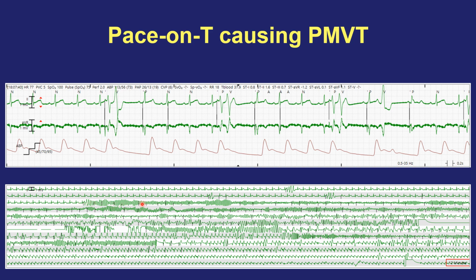Here is where polymorphic VT occurred. And it kept going until defibrillation occurred. But afterward, actually, this happened again, and it self-terminated, and again. And then finally, the sensitivity was appropriately adjusted so that these pacing spikes on T waves stopped occurring.